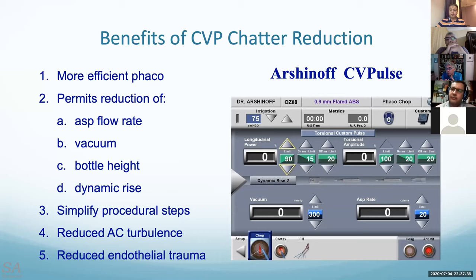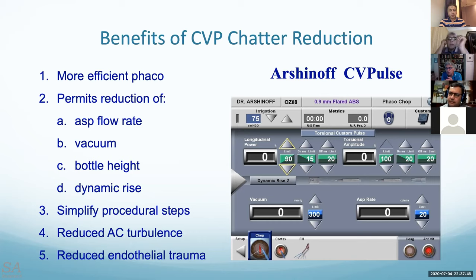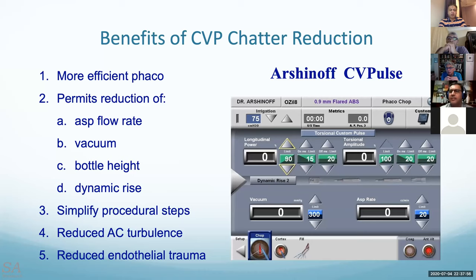Which machine to use — Infinity versus Centurion? Most cases are done on the Infinity, which is very familiar. The Centurion is excellent but less familiar. Both machines are well and good, but the first choice is the Infinity due to familiarity with parameter adjustment. The Infinity works extremely well; all these CVP settings were designed on the Infinity. The Centurion causes some hesitation due to lack of experience with its parameter adjustment.